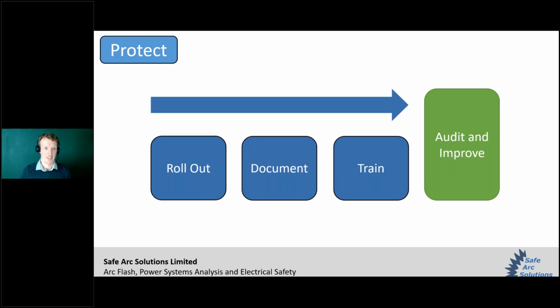And that then means that you can roll into protect, which means rolling out that Arc Flash strategy, of course. It means clearly documenting it in your site safety rules and procedures, and ensuring that people have the training and the competence to make it work. And of course, it's not something that you just roll out and leave. You should be monitoring it and improving it. Also, if you make changes to your system, if more switchgear is added, more motors are added, or a generator is added, this can change the Arc Flash values. So you really should be thinking about revalidating the numbers and revisiting how your strategy works in those situations.